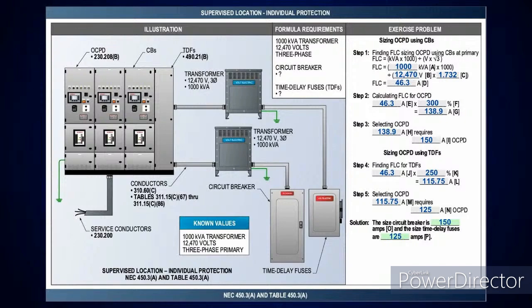One of the things that'll be interesting on the online portion of this, on the left-hand side when this is laid out, I will have a code loop for you to follow. I would tell you right away to go to table 450.3(A), then table 240.6(A). Then I would drop to the next one and say, all right, now let's look at table 450.3(A) again. Right here you're doing the time delay fuses, and it said to take it at 250%. That gives me 115.75 amps. So I go down to table 240.6(A), and the next size above that is 125 amps.